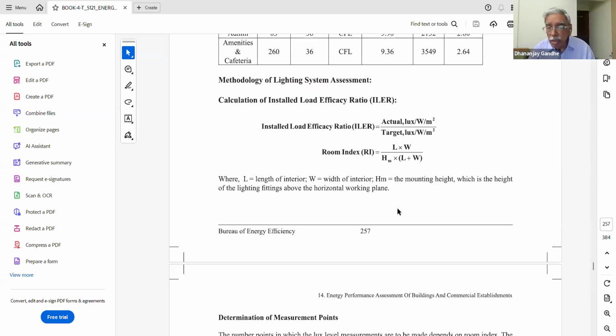This ratio is called the efficacy of lighting. As we mentioned when you studied lighting, we don't use the word efficiency. Lumen per watt, how many lumen we get from a lamp per watt of input, is not called the efficiency, it's called the efficacy. So that is called the efficacy of the lamp. Similarly, we don't use efficiency of the lighting system, but we call it the efficacy of the lighting system. So the performance parameter for the lighting system is the installed load efficacy ratio.